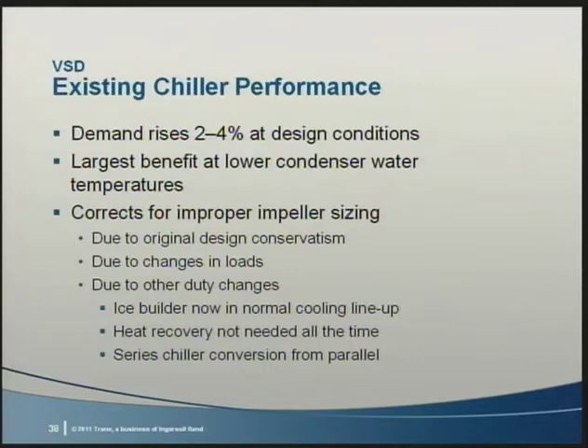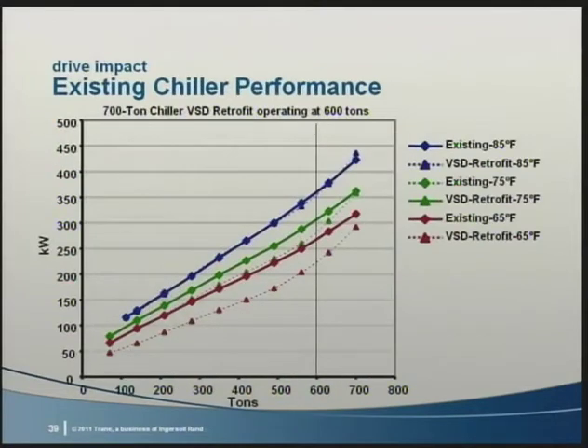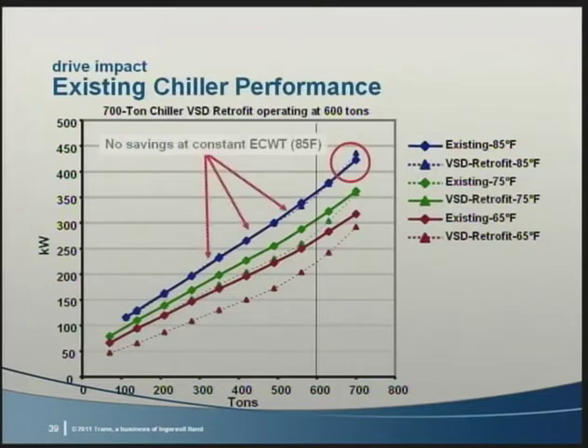The first thing to note is that at design conditions, kW rises. That's that 2 to 4% inefficiency of the drive that we pointed out before. Similar to the previous examples, let's look at a 700-ton chiller operating at a 600-ton load. Now next note that if the condenser entering water temperature is held constant, there's no benefit from adding a drive. So in a very humid climate, such as Singapore, Puerto Rico, Miami, or Houston, there may be no benefit in applying a variable speed drive to an existing chiller, since there's little to no lift reduction available.